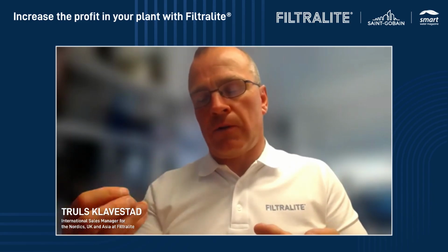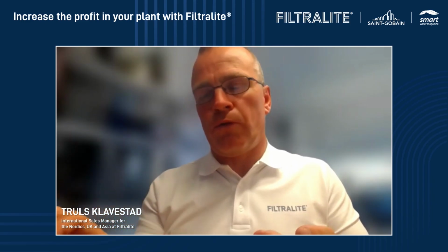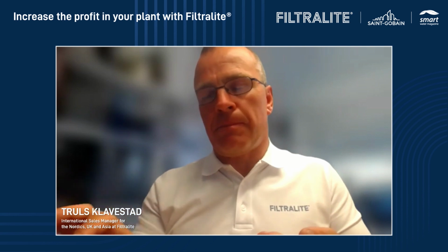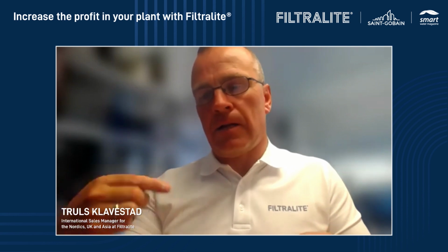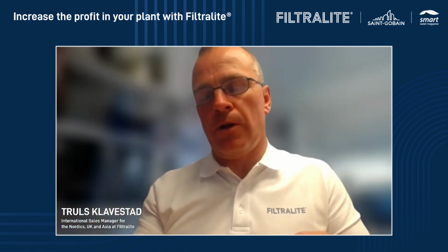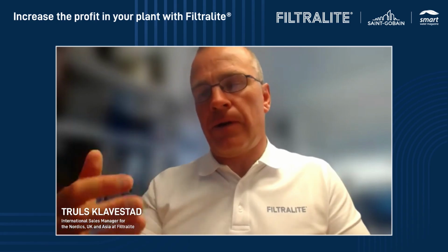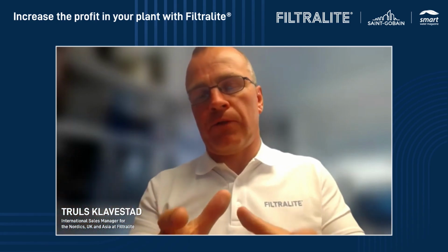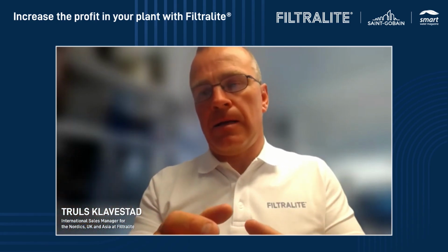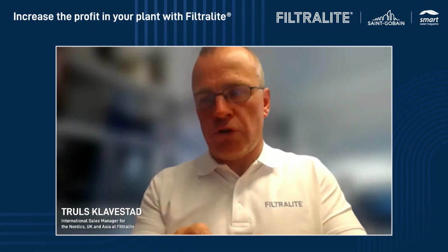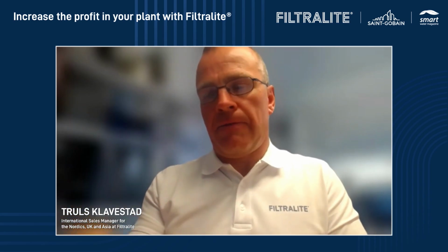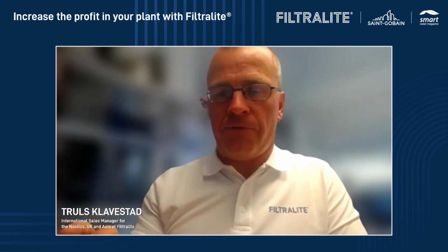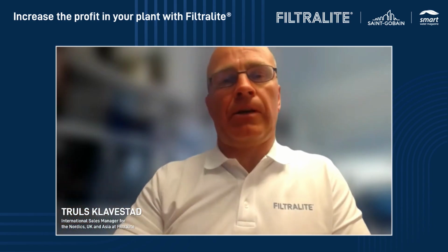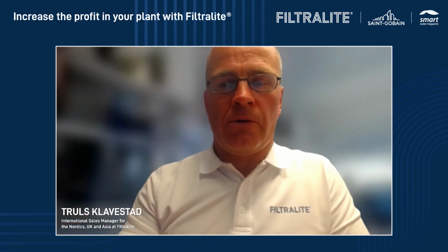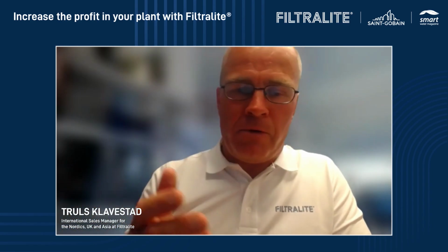Because activated carbon needs to be regenerated, you don't want to push that material too much, you want it to last as long as possible because of the cost of regenerating it. So very often they set in Filtralite first as a pre-treatment, and then they have activated carbon as a kind of polishing final step. So yeah, please contact me.